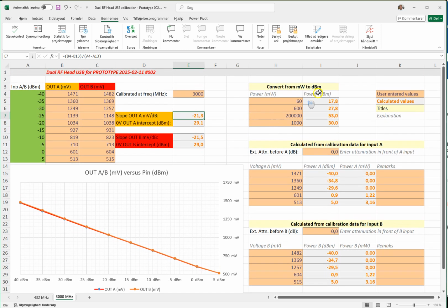On the right side of the spreadsheet, there's a couple of calculators. Just a simple one that will convert from milliwatts to dBm. And then there are two sections, A and B, that will calculate the power measured according to the voltage you type in. You can see here that I have typed in these three numbers, the same numbers as we have over here, the measured calibration values. And the spreadsheet then uses the data, the slope and the intercept points, and based on that and the voltage you type in here, it will calculate the power.